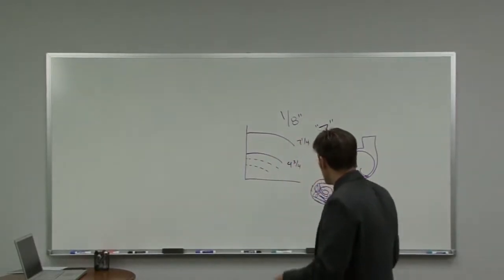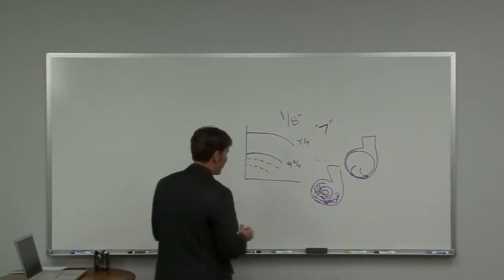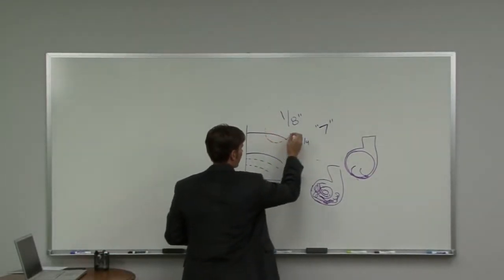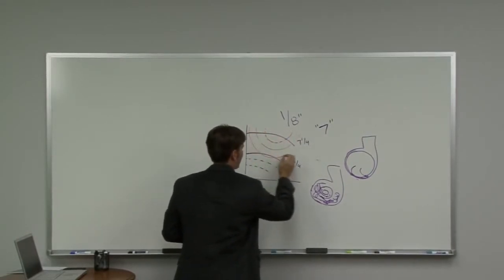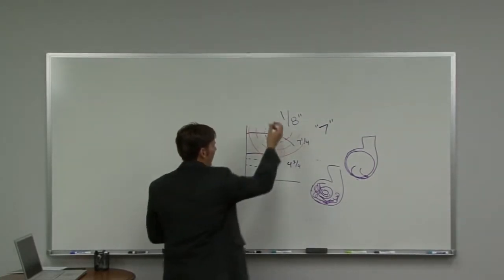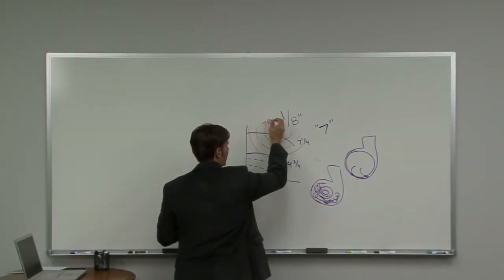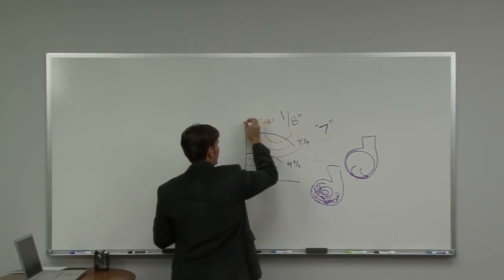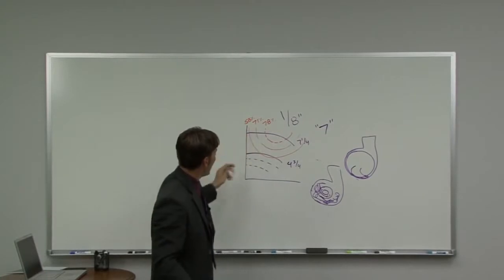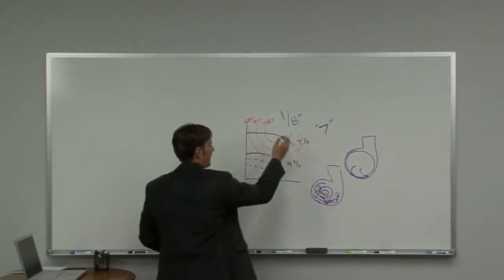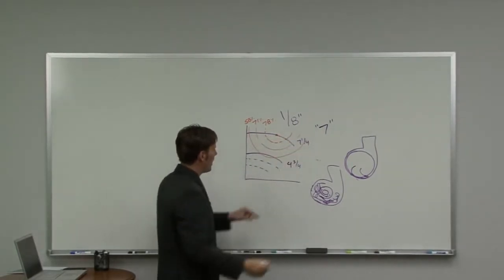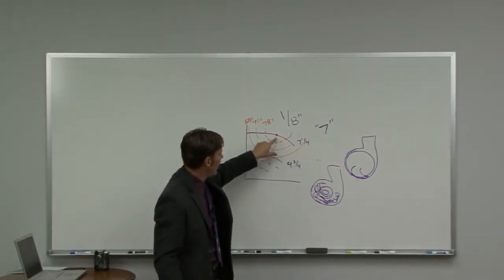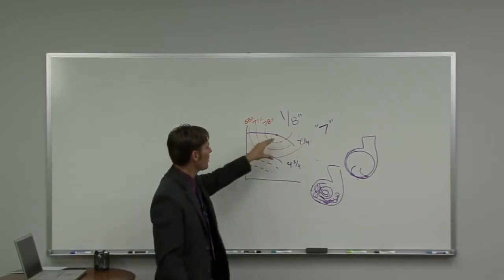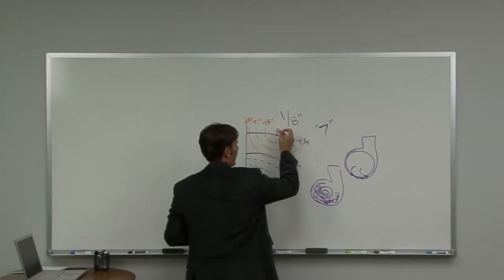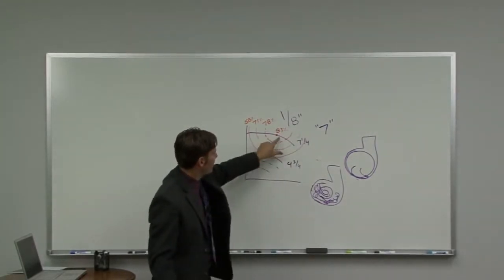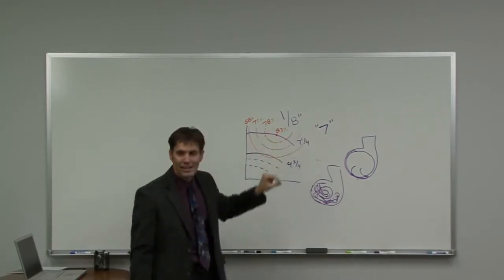The next thing I've alluded to is your efficiency curves. So let's take a different color here, and my efficiency curves will look like this. They're dropping through the pump like this. So let's just say this is 78%, and as we move further out, 71%, 58%. As you move further and further out, your efficiency lines are going to be less and less. If I could operate right here on this pump curve, on my maximum impeller trim, that could be my best efficiency point. I can't get any more efficient than that point right there. And with this pump, let's just say it's about 83% efficient. As I move further and further away from my best efficiency point, I'm going to be less efficient.